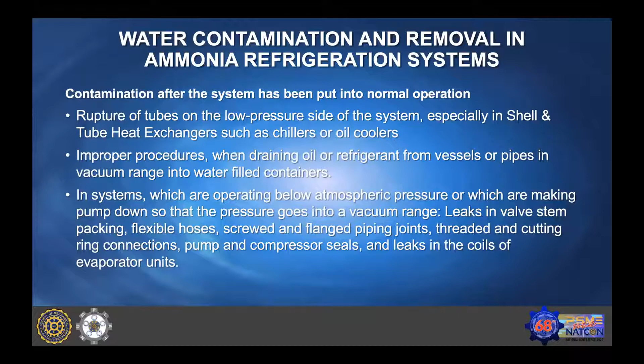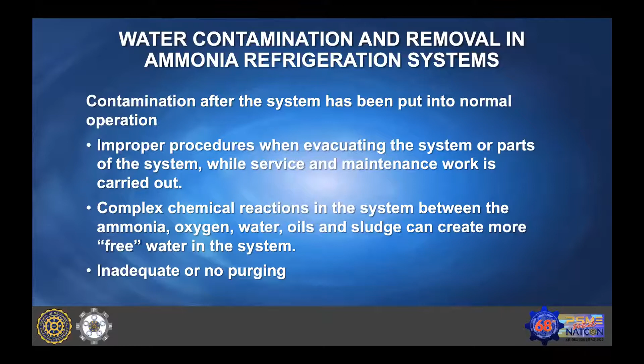And secondly, the most important thing is that when a plant is running in a vacuum and there is a leakage, along with the air, the moisture in the air will also enter the system. That leak may be through valve stems, flexible hoses, other connecting joints, or flanges. So when these improper procedures relate to air, water enters the system and remains in the system. And when this water remains in the system, chemical reactions start taking place between ammonia, oxygen, water, and oil, and it forms a sludge or free water in the system.